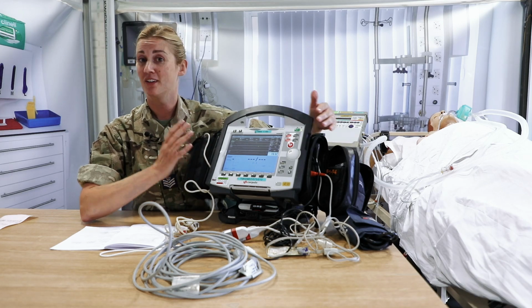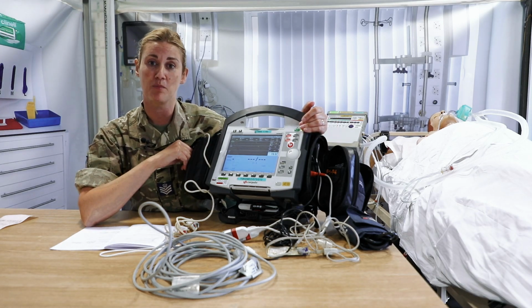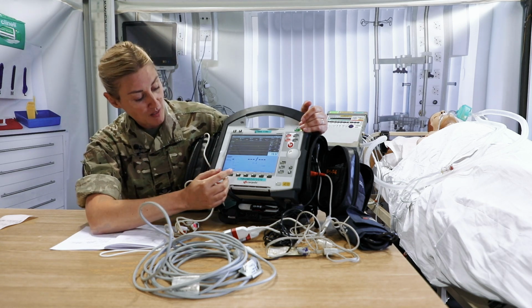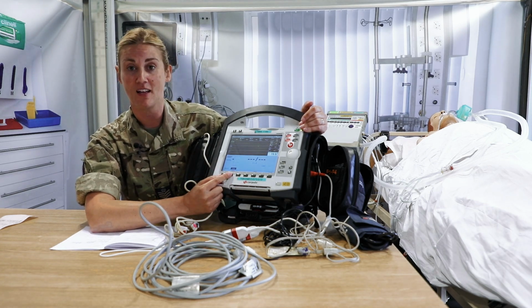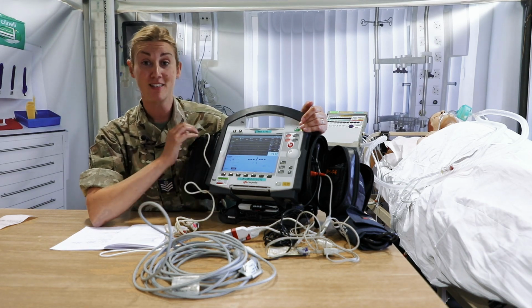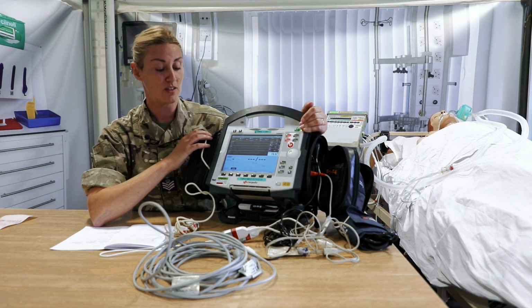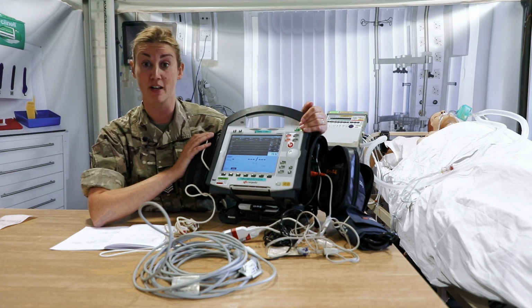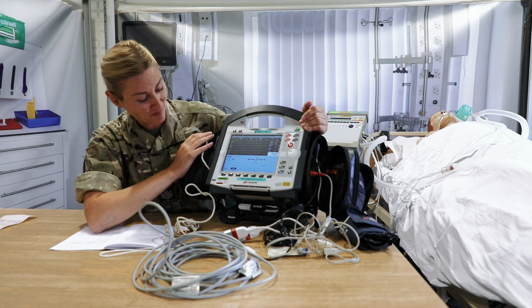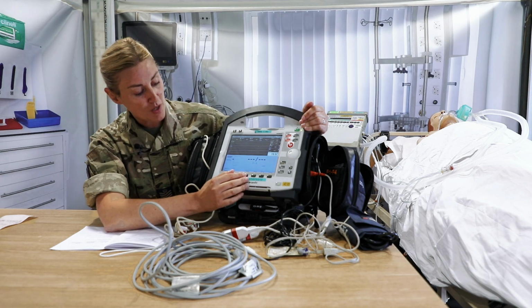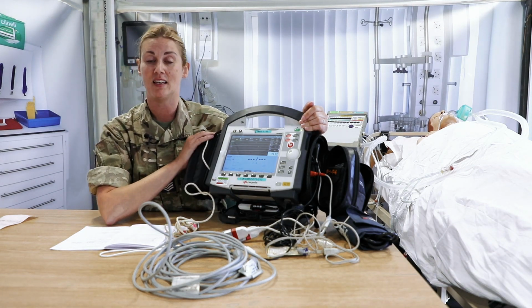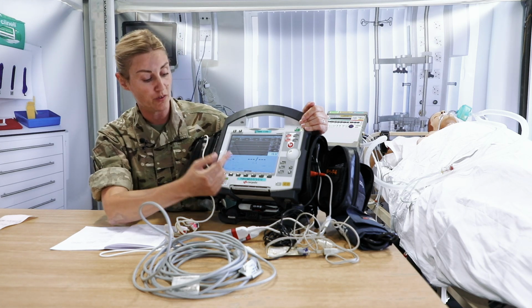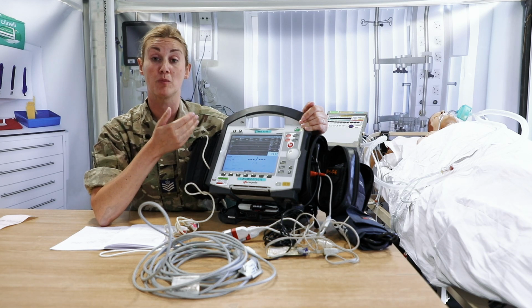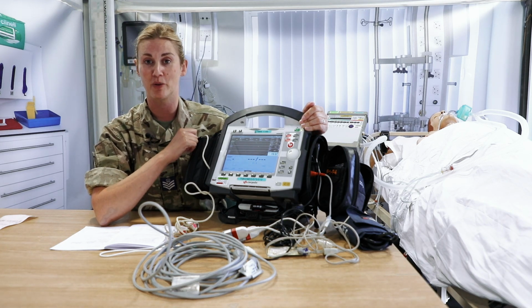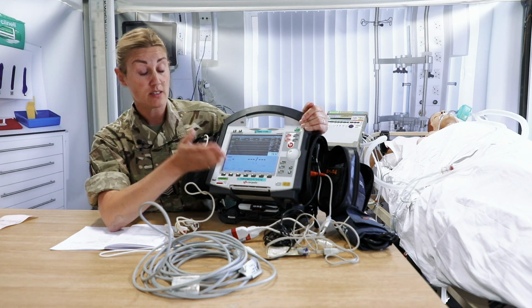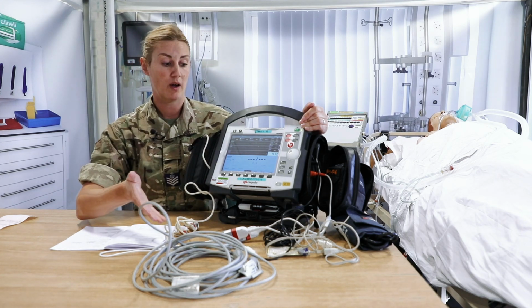So you're going to put the cuff on, you or a friend, and check that the blood pressure cuff actually functions. If you want to be kind to your friend, then you can adjust that initial inflation pressure. It's currently set to 200, so if you know your friend's blood pressure isn't anywhere near 200, then you can adjust that initial inflation pressure if you want to, or not. It's up to you. Selecting there, you can have a look to make sure that you can set an automatic blood pressure taking. So if you press the auto function, then it starts to give you some options for how many times you want to take that blood pressure and how frequently. So confirm that it takes a blood pressure successfully, and then we'll work our way through the leads.